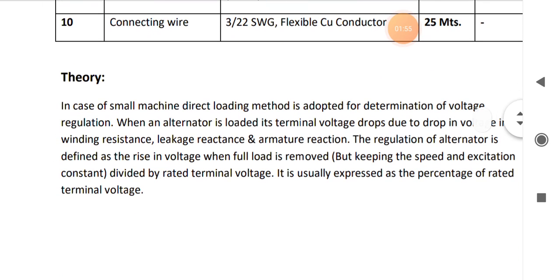Now the theory. In case of small machine, direct loading method is adopted to determine the voltage regulation. When an alternator is loaded, its terminal voltage drops due to drop in voltage across winding resistance, leakage reactance and armature reaction. The regulation of alternator is defined as the rise in voltage when full load is removed but keeping the speed and excitation constant, divided by rated terminal voltage.